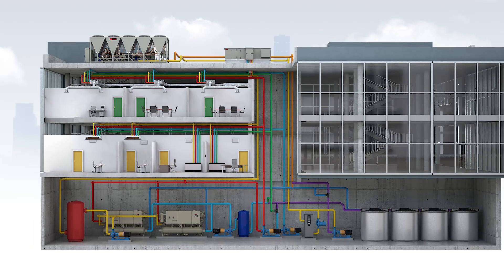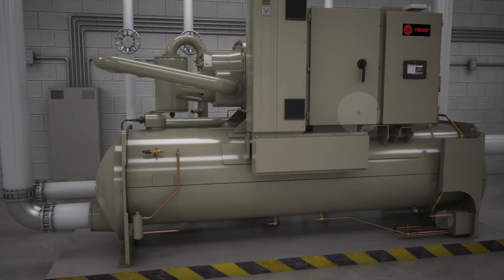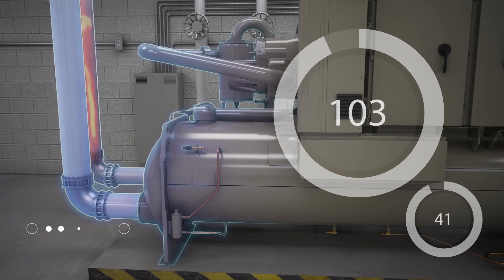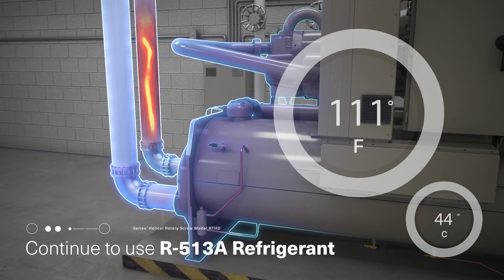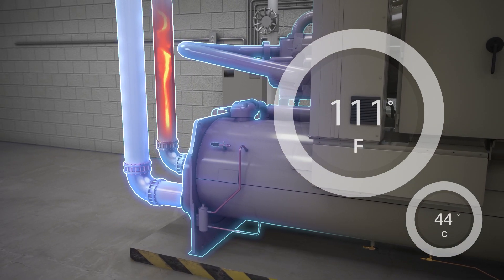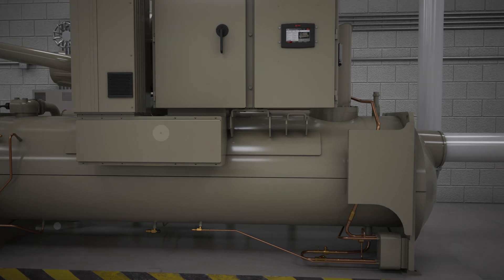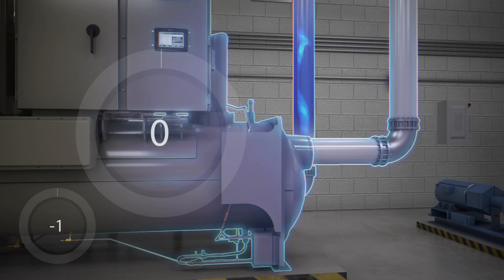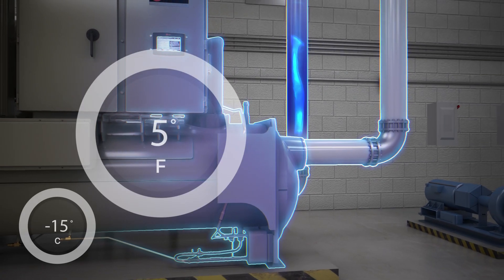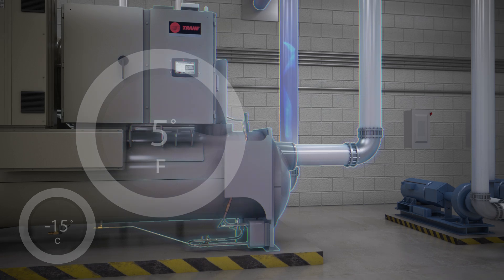The RTHD will, likewise, continue to use its R513A refrigerant for all applications, which offers a 55% reduction in global warming potential compared to 134A, and can be configured to produce 5 degrees Fahrenheit leaving solutions temperatures.